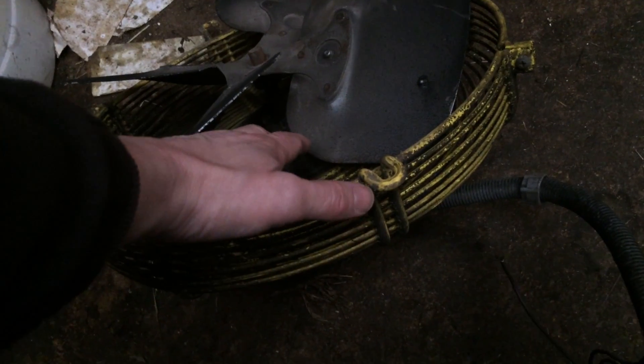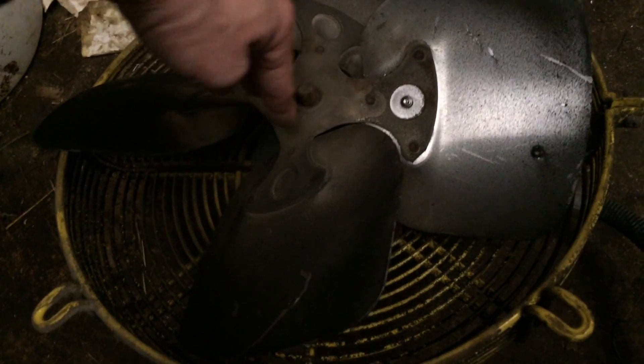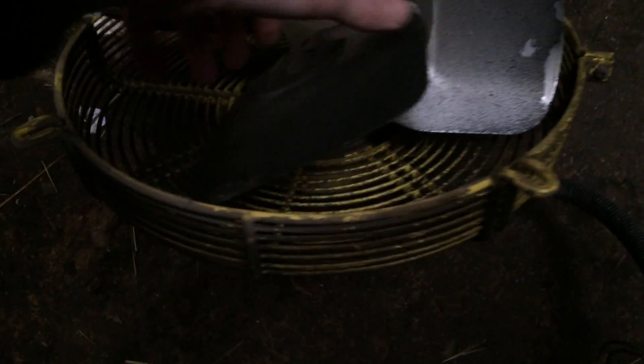Quite often what you get when the bearings go is once you've got the magnetic field in there, it sort of pulls the rotor across to one side and makes it drag. So quite often you can spin them, but not very well by hand, but as soon as you power them up, they seize up solid.